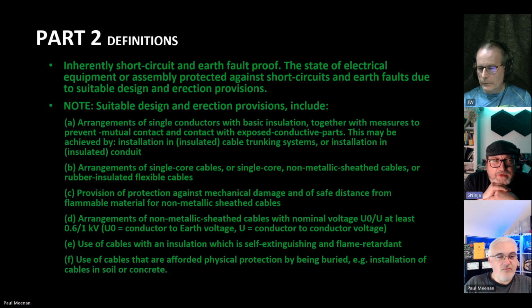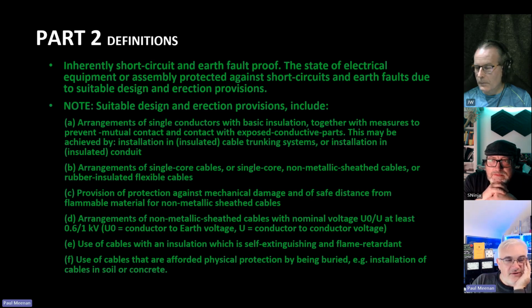Right, so putting basic cables in an insulated system to make sure it doesn't make contact with any outside earth environments. Yeah, this is basically class 2 equipment, but it's class 2 for installations. Yeah, it is. So we're going to be doing plastic conduit everywhere. Well, it's identifying that if you have a steel conduit or a metal trunking system with singles in, there's a risk inherently of having earth faults going to extraneous or other parallel pathways. But if it's an insulated system, it should have earth fault protection at least. I'd like to see a bit more guidance on that bit actually.